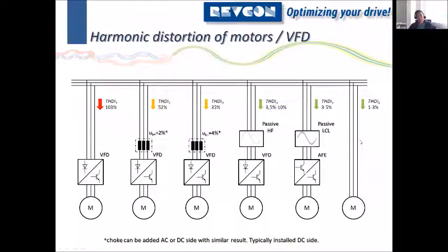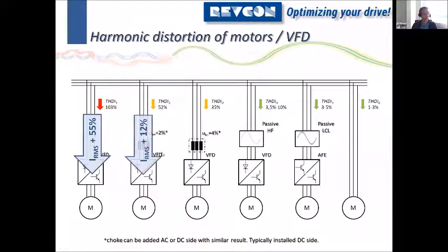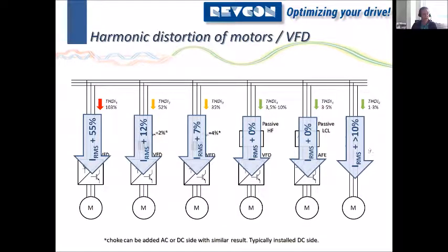So the first disadvantage of these kinds of solutions, or the disadvantage of the high THDI, is the input current. So if we look at 103% THDI, that means your input current will be 55% higher than it had to be if you had a pure sine wave input current. The next setup with the 2% choke, 52% THDI, would still have a higher input current of 12%. 35% THDI would still result in 7% higher IRMS compared to the clean solution, passive harmonic filter, or active front-end solutions. And obviously, motors direct online will cause higher currents because of the reactive part they cause. They have a power factor, cos phi, so they would typically at least pull 10% higher RMS from the grid, probably higher.